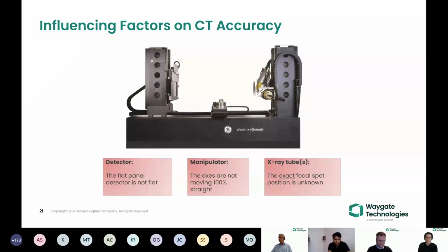A CT scanner always looks kind of the same. You have some sort of detector, like in this case, a flat panel detector down here. You have some sort of CNC stage, some rotating table that is able to move up, down, left, right, back, forth. And you have one or two or even more X-ray sources here on the right-hand side, so X-ray tubes. As you can see here, everything is marked red, so everything has its own issues when it comes to metrology. These systems work fine and perfectly for many, many years for standard CT analytical scans. But if you want to do metrology on a very high level, with a very high accuracy, keep in mind that I said you have to choose the right equipment for your application. If your application means we want the highest accuracy, then we have to take care of these issues. And the first one is our detector.